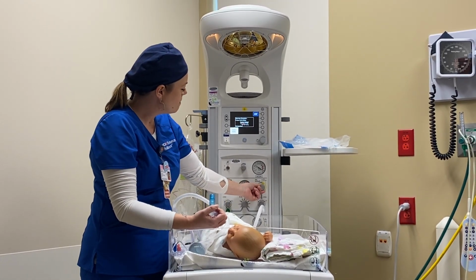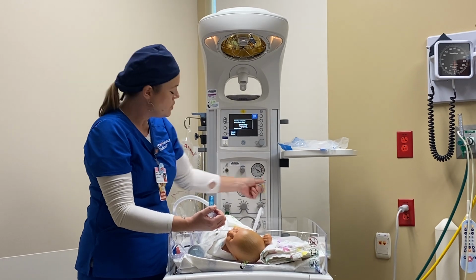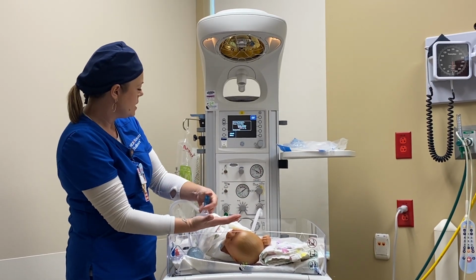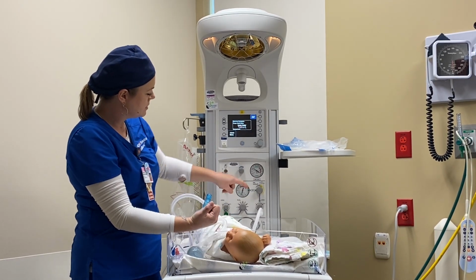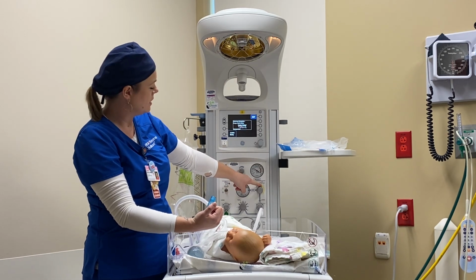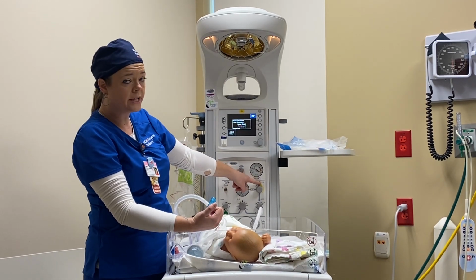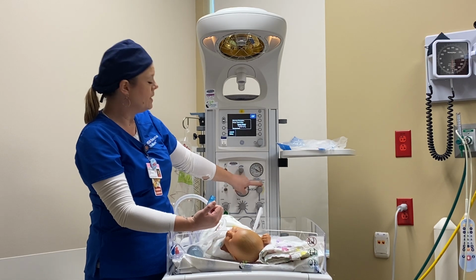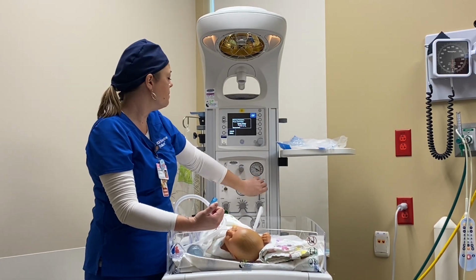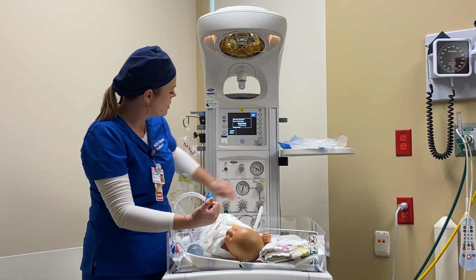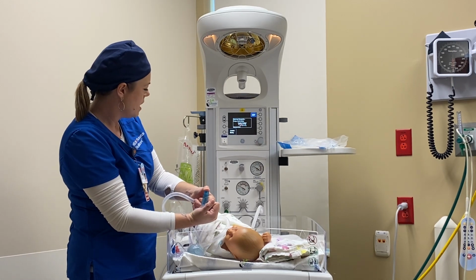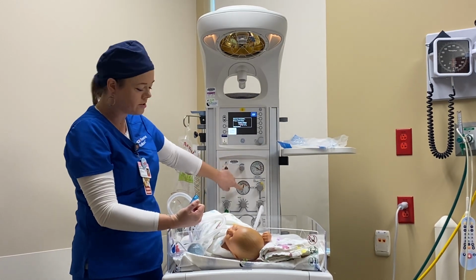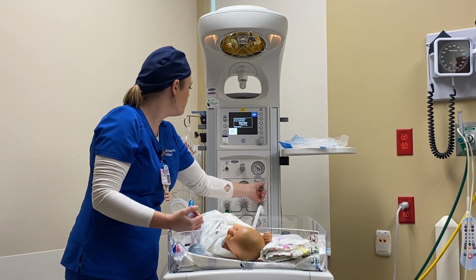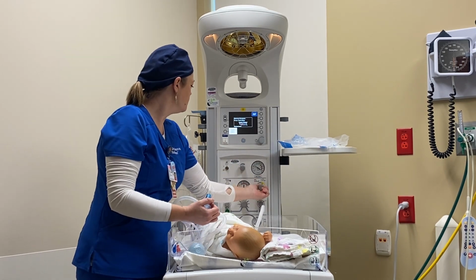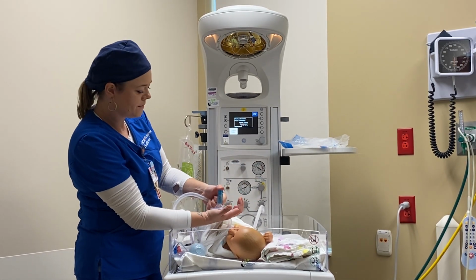You want to adjust your PEEP or your PIP here, and you can go up to a max of 30 before you hit this little yellow dial here, which is telling you that's a lot of pressure and you're in danger of blowing a pneumo. So be cautious about going over that. But if you push the little dial in, you can go past it, and I can achieve an even higher pressure. But that does put you in yellow and then red. So again, watch that very closely. We want this guy back down to 20 for a proper resuscitation.